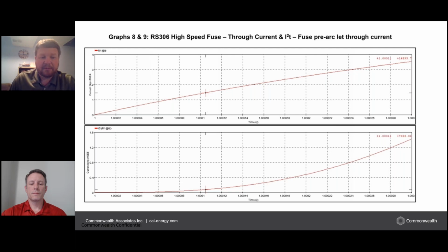performance. However, if the fuse is slightly slower than the DC rise, then we have to use the prospective currents, which, as Chris mentioned and showed earlier in his presentation, can be substantial and significant. So this graph that we're looking at right here, I'll flip back real quick. We'll just wrap up. This had a prospective fault current, I think, of 185 kA. And what we found is this particular fuse and the L over R combination of the circuit, our fuses were blowing at approximately 15 kA.